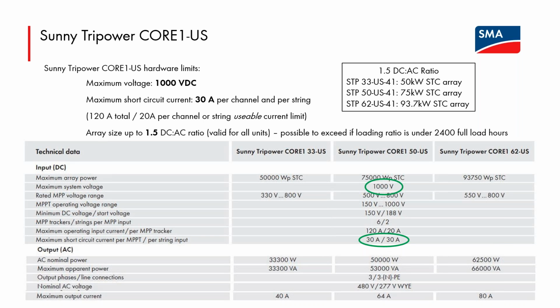And I do have a slide a little later. It references both the CORE1 and the PEAK3. If you do wish to exceed that data sheet DC to AC ratio, SMA is going to ask you to construct the site-specific design in our design tool. So the actual modules you're planning to use, how they're mounted, wired up to the CORE1. When the simulation is done, not only will the design tool show an expected kilowatt hour or megawatt hour per year yield, it will also produce a metric called full load hours. If that full load hours stays under 2,400, you can safely exceed the datasheet DC to AC ratio without voiding your warranty. You always have to respect the maximum open circuit voltage and short circuit current limits. And again, just to be clear, if you're satisfying those 2 limits, you can go up to this 150% ratio without any further conversations with SMA. It's only if you wish to exceed that ratio that you need to do the Sunny design calculation.